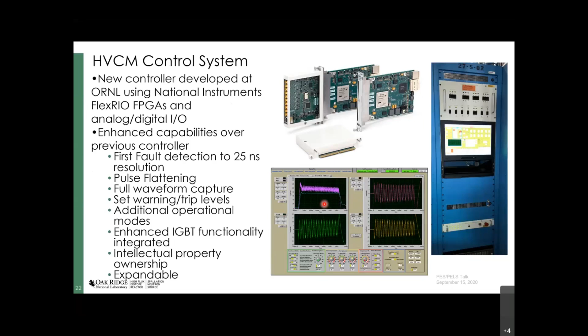Not only can we detect events at 25 nanosecond resolution, but if we detect a fault event, we can shut down in less than a microsecond. This helps protect against delivering too much energy into the klystron load and damaging it. We can also use a variety of modulation techniques, pulse flattening, full waveform capture, and waveforms can be stored during fault events for troubleshooting later, among other things. So we've gone from the dark ages to something a lot more modern, which has been a great advantage to us.